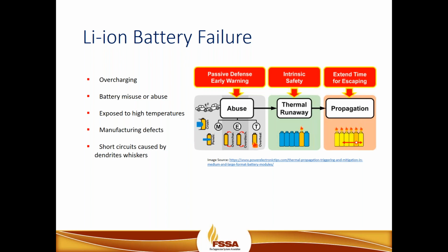So if you look at what causes battery failure, we're going to look at some of the abuse factors that could cause battery failure, but really we're going to focus on two main abuse factors during this presentation, and that is overheating and overcharging. They are the most common and the most preventable abuse factors. Additional abuse factors for battery failure could be external damage to the battery and even direct penetration of the battery. These types of abuses are known as mechanical abuses, and of course, we cannot prevent mechanical abuses. So the problem really relies in once the abuse factor occurs and nothing is done to stop, mitigate, or prevent the abuse factor from continuing.